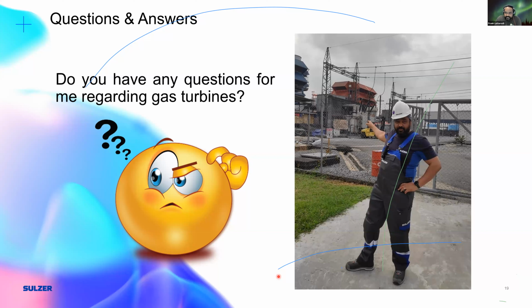With regard to the different types of gases, I'm not very conversant, but I know we usually have a chromatography device that tells us a lot about the gas we're using, in terms of its calorific value and composition. For the control system, we have to take certain things into consideration, like the density of the gas and the calorific value, because it determines how I pre-position my control valves. If I position them too wide, I would have an explosion; if too low, I won't have the demand required. So we rely on the input from gas chromatography devices, and I wouldn't really know everything upstream of that point.